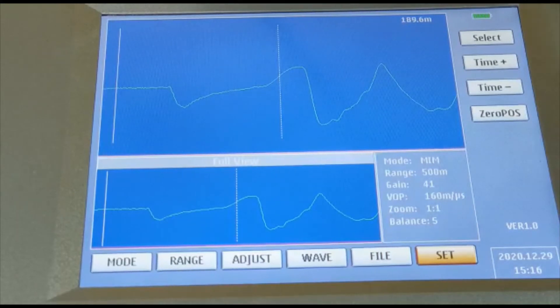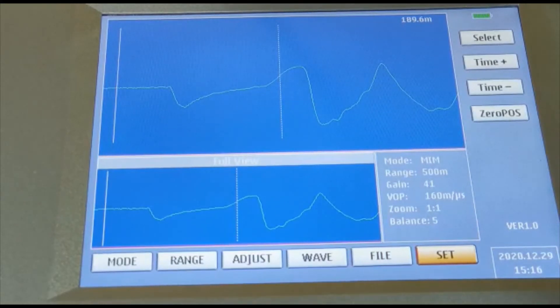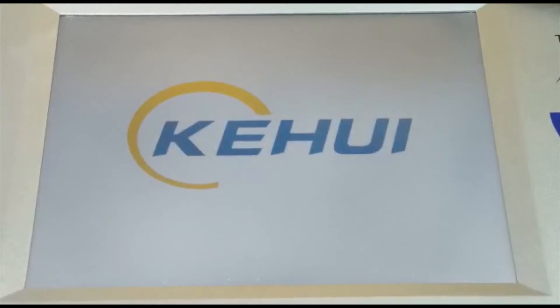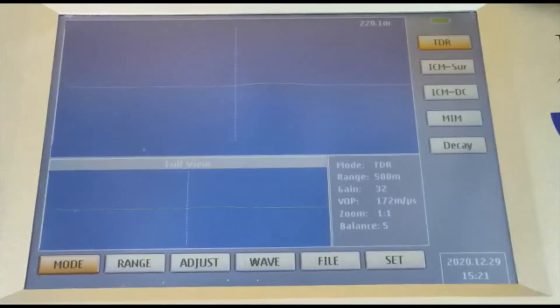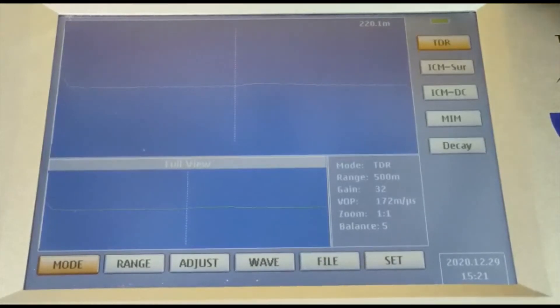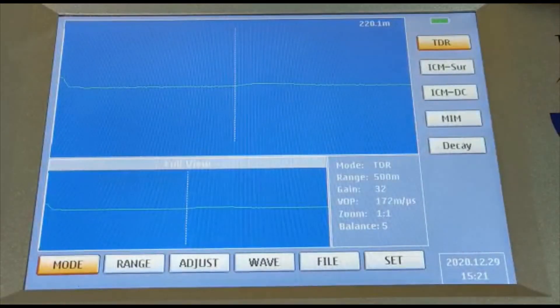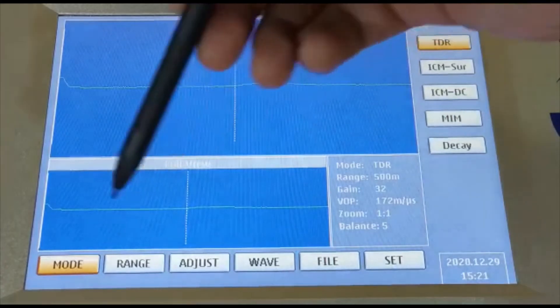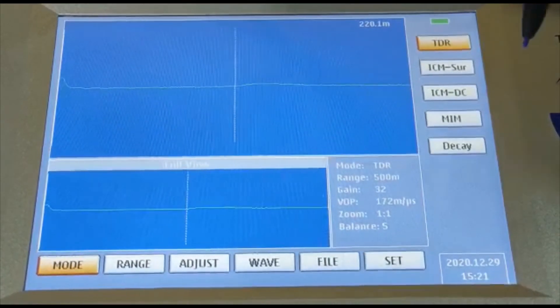I hope this video gives you more information to understand the T906 cable fault locator. Now we will demonstrate on different distances of cable faults and show you how open circuit and short circuit faults occur and can be identified using the T906 cable fault locator. First of all, when you switch on, make sure you are using TDR mode.